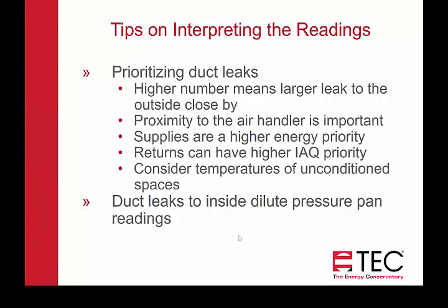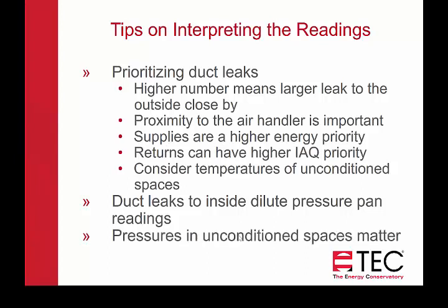This is a very important building science principle: duct leaks to the inside will dilute your pressure pan reading. If most of your ductwork is in the house inside the house and you just have a few runs in the attic, and there are a lot of duct leaks to the inside, those are going to dilute your pressure pan readings a lot and you're not going to get as much information from those readings. Pressures in unconditioned spaces matter. If you've got a well-vented attic with ductwork running through it, and your house is at 50 pascals, and you measure the pressure to the attic and it's close to 50 pascals — that's going to be a lot different than if the attic pressure is only 20 or 25 pascals.